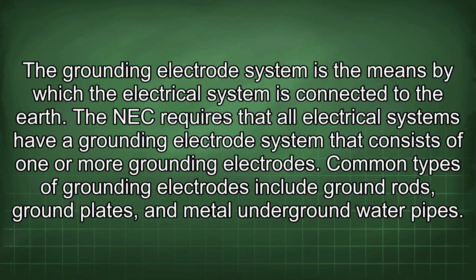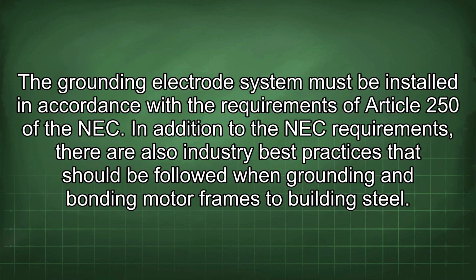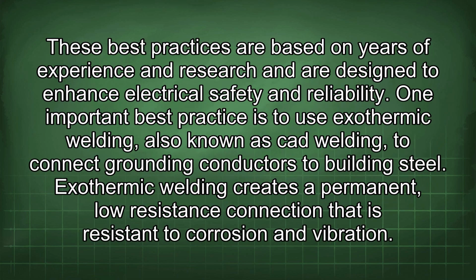The NEC requires that all electrical systems have a grounding electrode system that consists of one or more grounding electrodes. Common types of grounding electrodes include ground rods, ground plates, and metal underground water pipes. The grounding electrode system must be installed in accordance with the requirements of Article 250 of the NEC. In addition to the NEC requirements, there are also industry best practices that should be followed when grounding and bonding motor frames to building steel. These best practices are based on years of experience and research and are designed to enhance electrical safety and reliability.